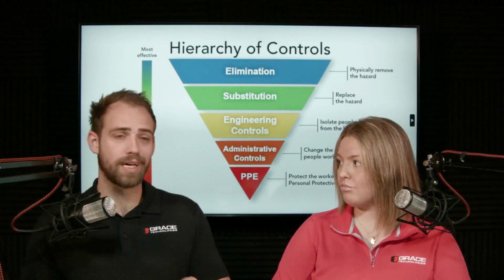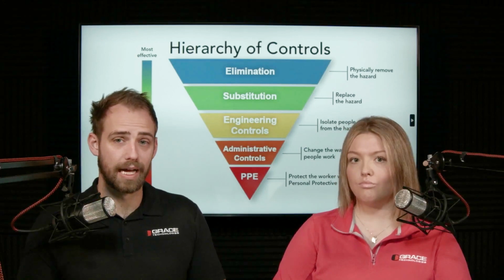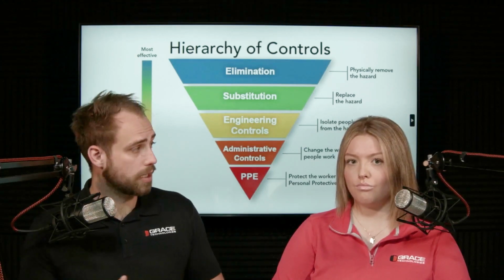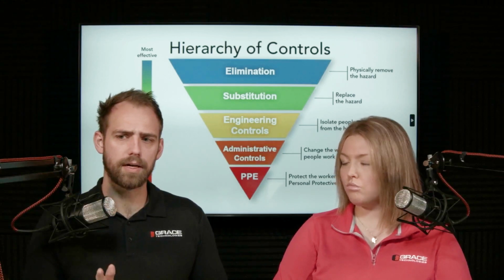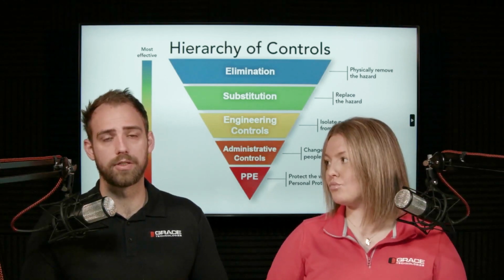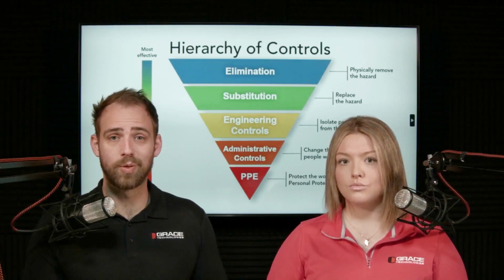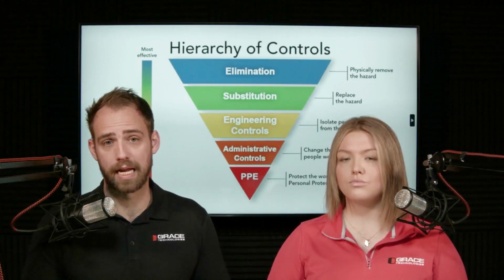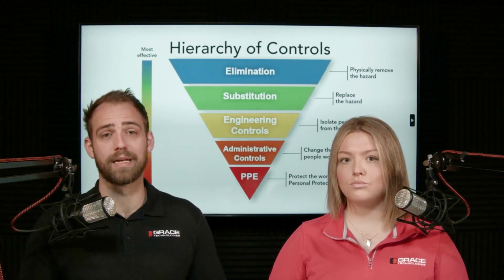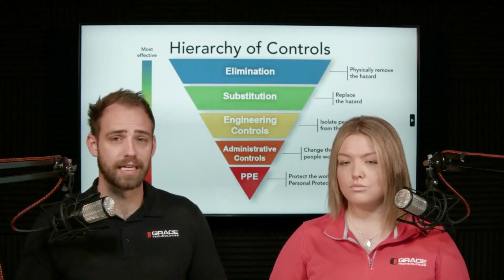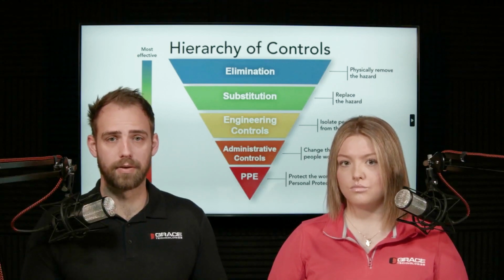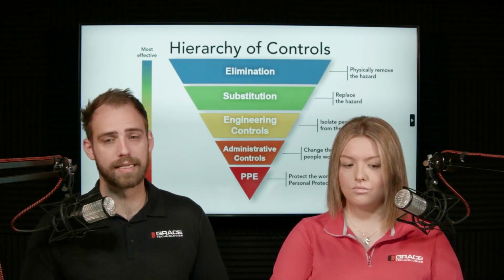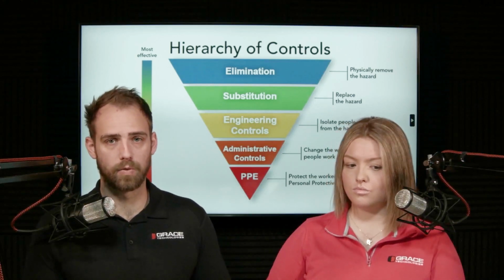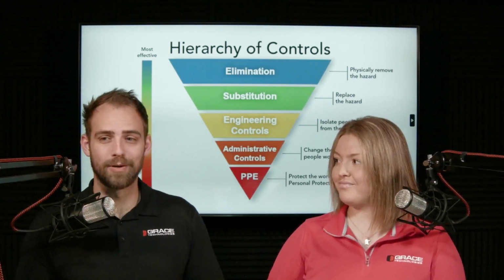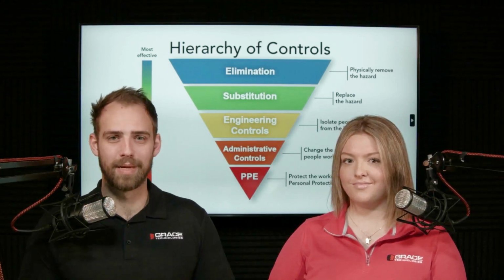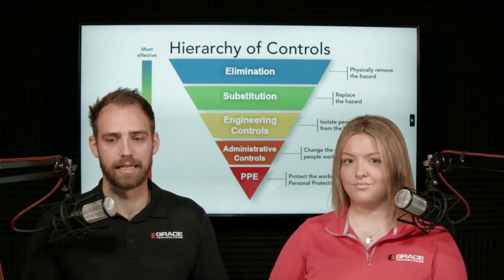You can plug your laptop into a GFCI outlet. Nick mentioned yesterday it's NFPA 79, if you have a GFCI outlet within the panel, you have to test it, I believe once a month according to those standards. Having that outlet right outside the panel makes it a lot easier, you don't have to open it up, it can be tested right outside the panel. This complies with those standards and makes procedures easier and faster, plus new employees don't have to fiddle around inside the panel touching something they shouldn't, causing an accident.